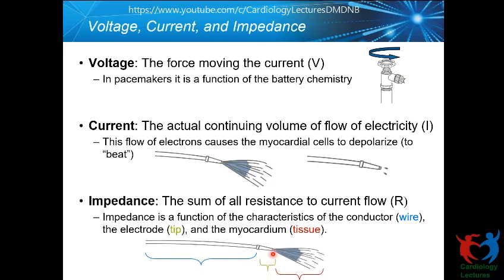And then the lead tip electrode also provides a certain amount of impedance, and at the interface there is a little bit of impedance for the flow of electrons into the myocardium. And then there is a little bit of polarization that happens at the lead tip, so that also affects the flow of electrons. So what we measure at the time of implantation and at the time of follow-up is a total of all these impedances. Essentially, we should have a lower lead conductor impedance, which is by design, and also a lower interface impedance, but a slightly higher polarization impedance. So this makes the total impedance somewhere between 500 to 1000 or 1500.